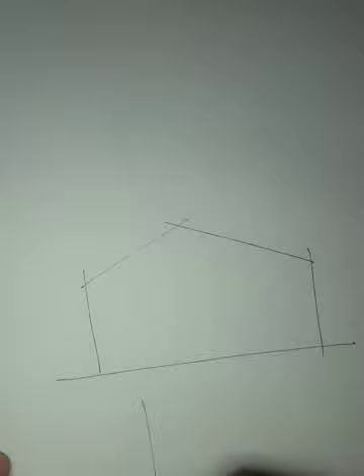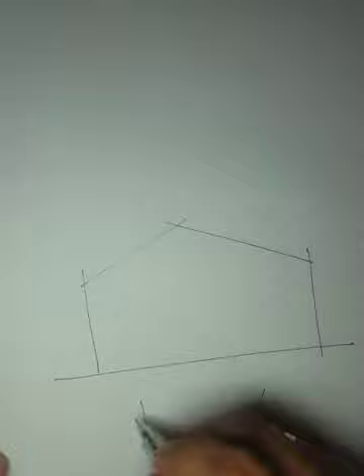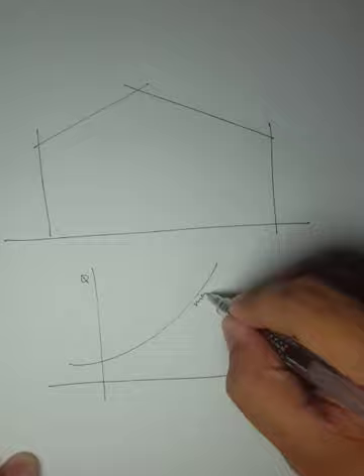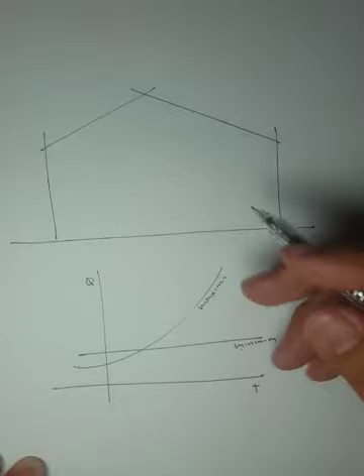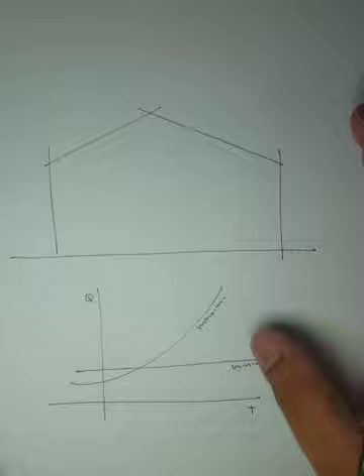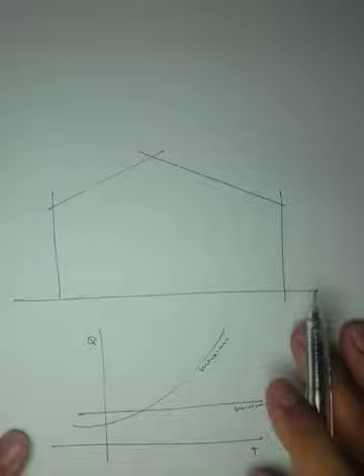We calculated ventilation rates at any ambient temperature, giving us a curve for maximum and a curve for minimum rates. The minimum rate is for moisture control and the maximum is for temperature control.